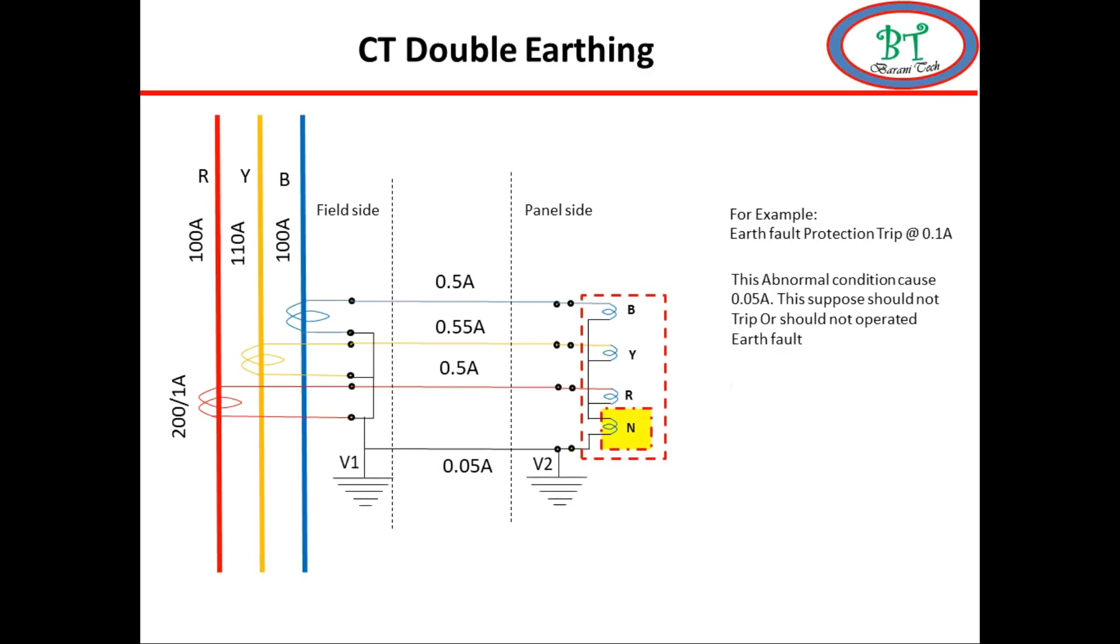But due to multipoint earthing sometime the potential difference may occur due to different resistance value on the earth point. Which lead to additional current flow on neutral line. This may exist more than settings value and which lead to trip.